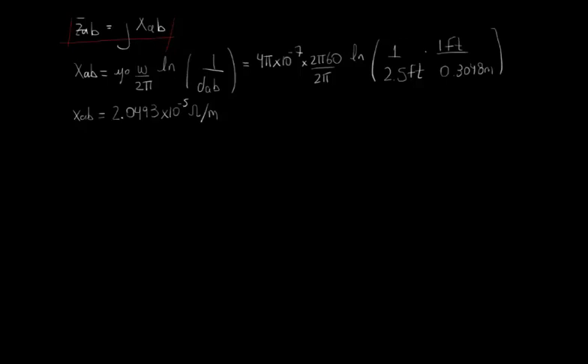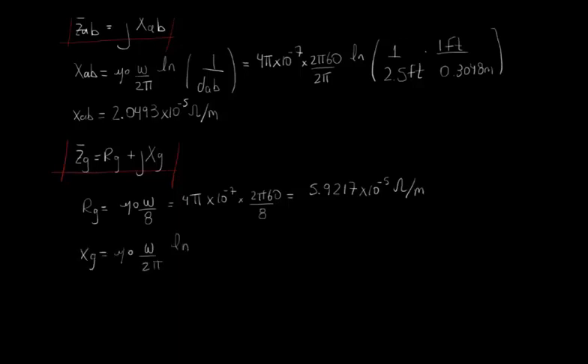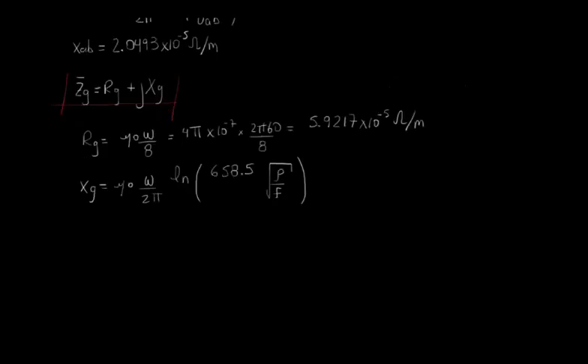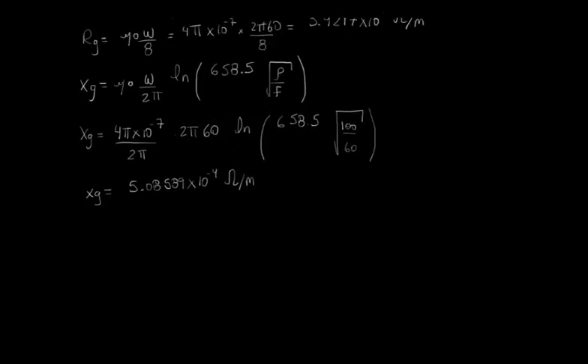Now, let's calculate RG and XG. Applying the first term of Carson's equations for RG, we find that it is equal to 5.9217 times 10 to the power of minus 5 ohms per meter. And for XG, that it is equal to 5.08589 times 10 to the power of minus 4 ohms per meter as well.